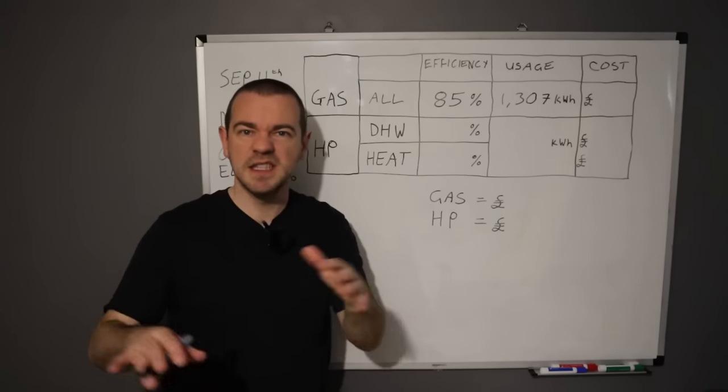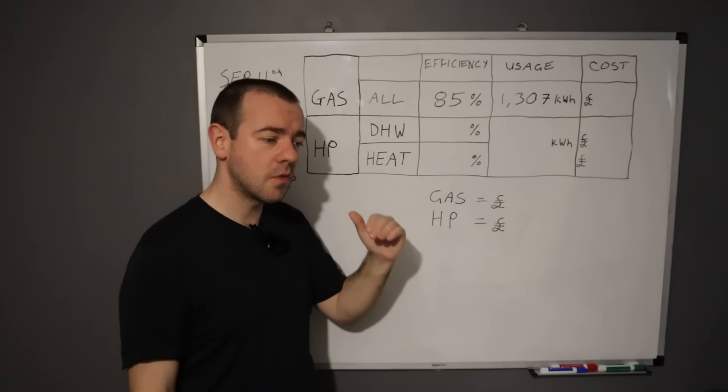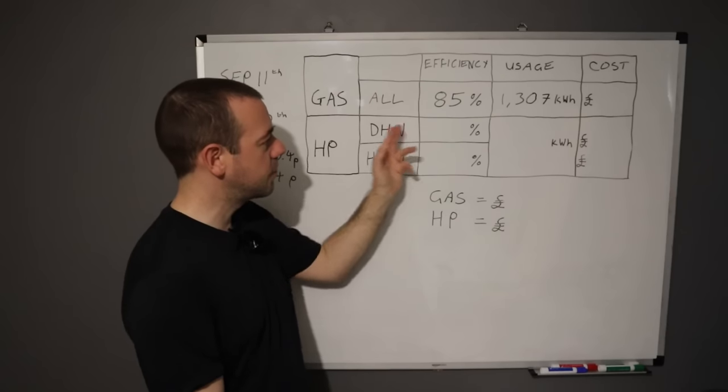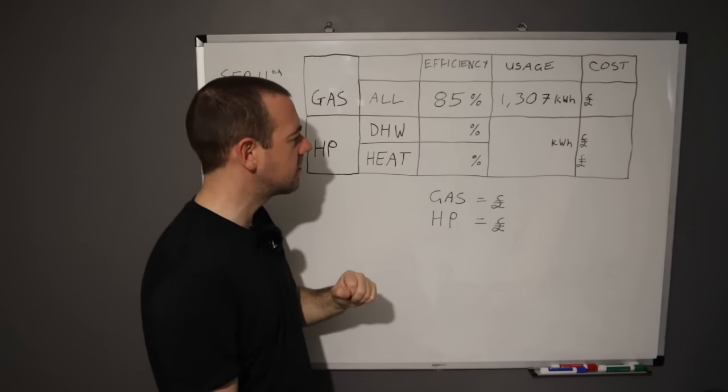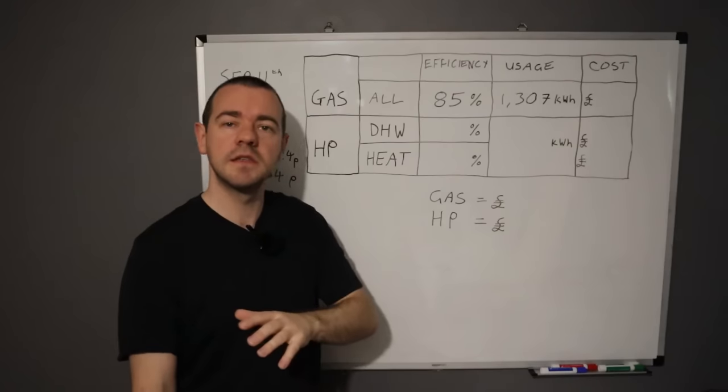DHW or domestic hot water, which to you and I is just hot water, and then the heating, the central heating system essentially. In terms of hot water which is now different for us, we've got a hot water cylinder that's heated up at night by the heat pump to 51 degrees centigrade.